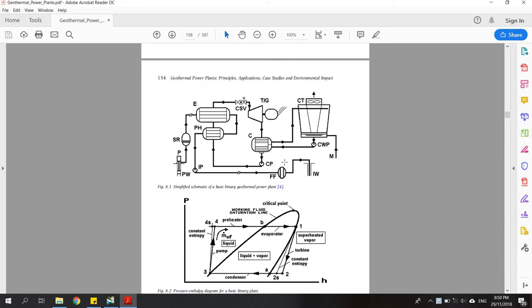As you can see here, the geothermal brine, which is still hot, will be used to heat the secondary loop, which usually uses a working fluid other than water. In this case I will use isopentane. There will be two heat exchangers: the first one is the evaporator and the second one is the preheater. The heat from the geothermal brine will be extracted through the evaporator.